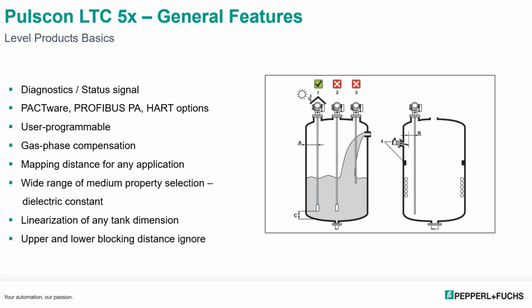Now off to the right, we show some yes and no's on how to mount it. The correct one is near the tank wall, and what this does is the tank wall actually acts as a return signal for the guided wave radar system. And you never want to put it in the stream of the water because you can't really map that out. If it was a stationary ladder there all the time, yes, but sometimes the water's coming in or the liquid's coming in or not. So the one on the left is probably your best solution for mounting.